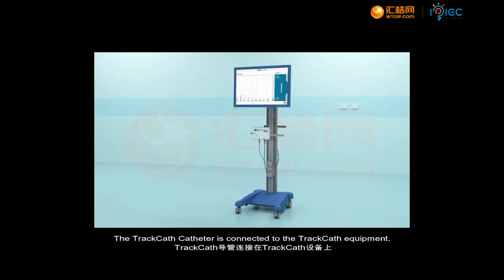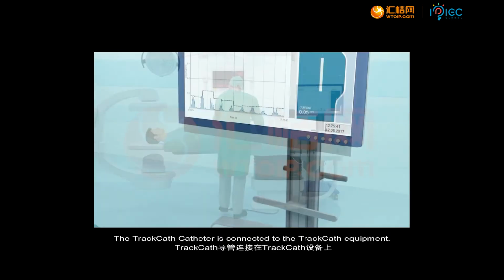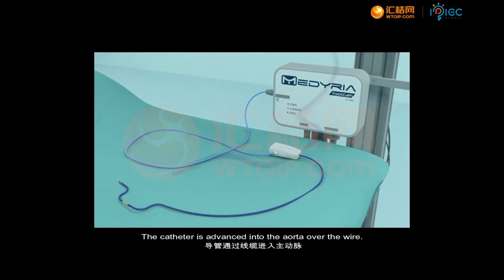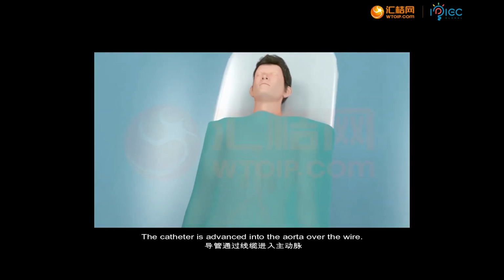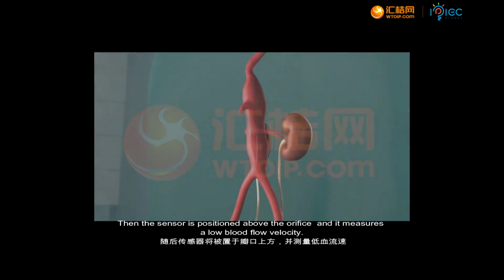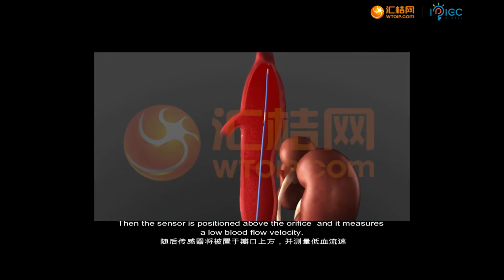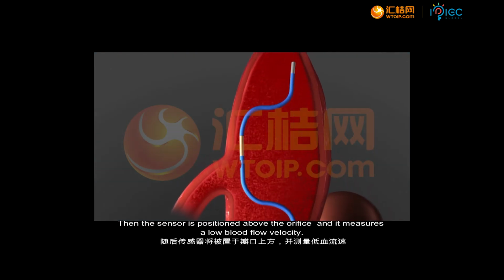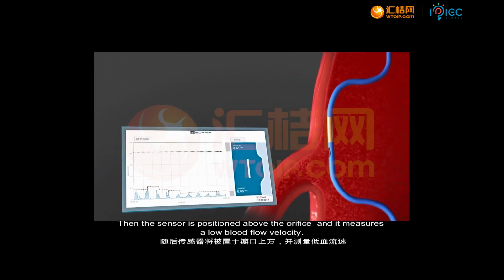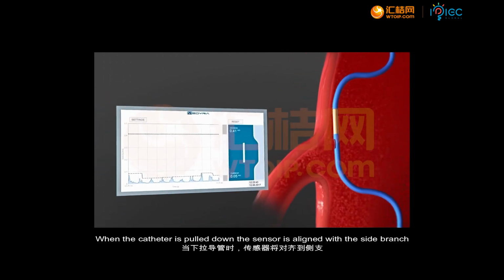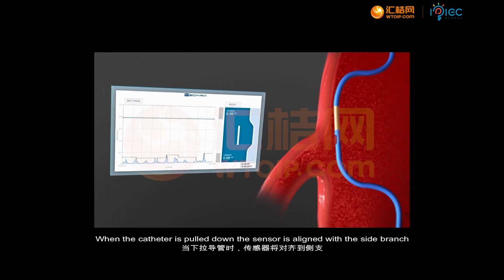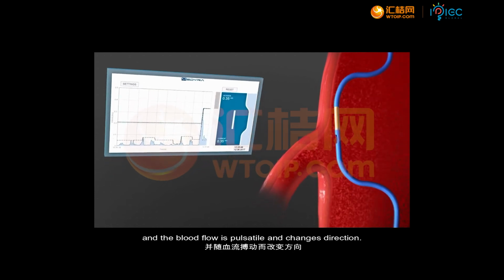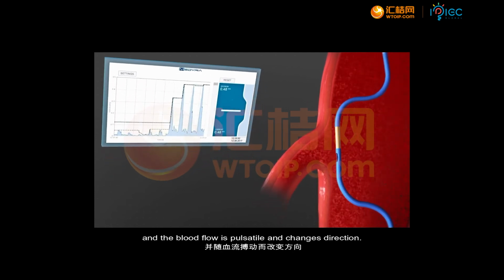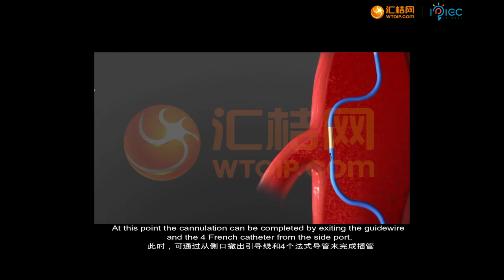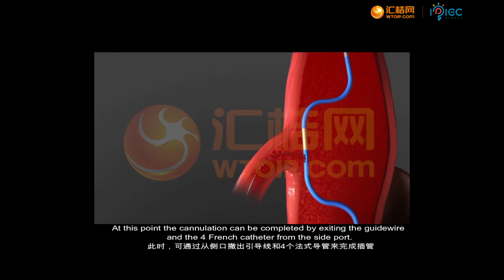The TrackCath catheter is connected to the TrackCath equipment. The catheter is advanced into the aorta over the wire. Then the sensor is positioned above the orifice and measures a low blood flow velocity. When the catheter is pulled down, the sensor aligns with the side branch and the blood flow becomes pulsatile and changes direction. At this point, cannulation can be completed by exiting the guide wire and the four French catheter from the side port.